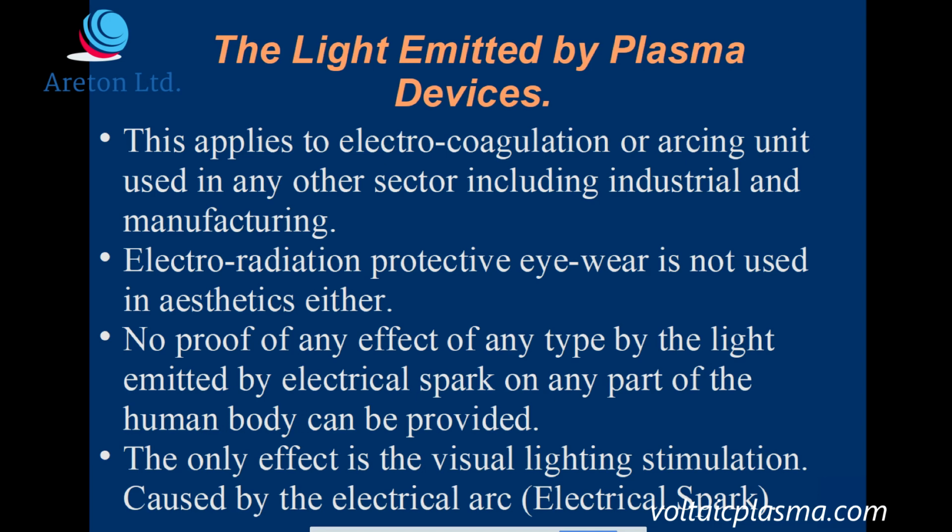But the point is that in any application, there's no requirement to have any protective eyewear in order to be near them. The main point is that electrical arcing devices do not emit a high intensity electromagnetic radiation which has any impact whatsoever onto the skin. And that is very, very important, let alone the eyes.